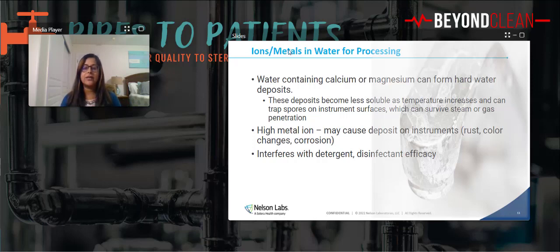High metal ions, rust, color changes, corrosion - you'll hear me keep saying corrosion, rust - because when you put all of these together, water is in the middle and everything becomes a web, it all stretches out. But water is the core of reprocessing. If you don't have the right quality, you create this big web of problems. I like to see it in that context: here is water, and then we have the ions, conductivity, temperature, detergents - all these tangents that go all around that we have to worry about.